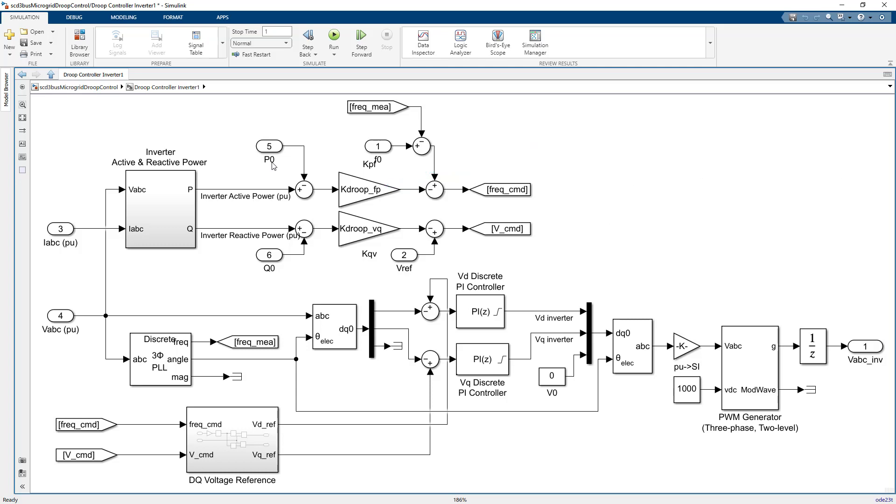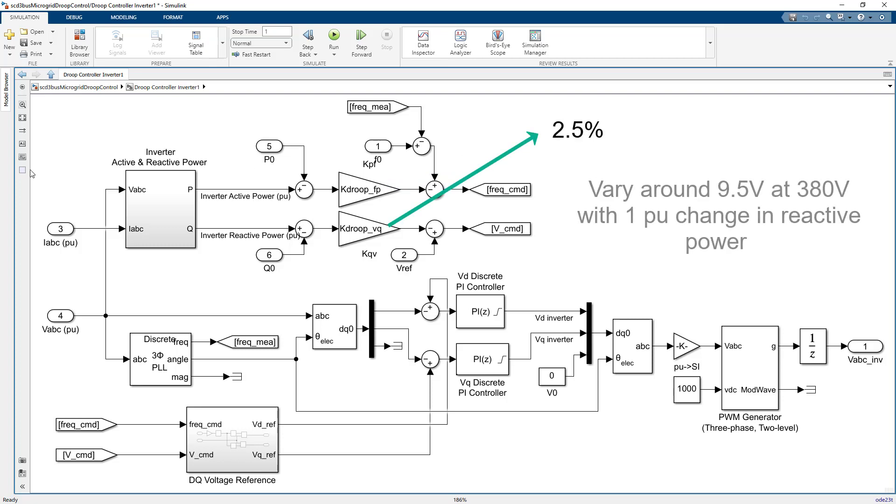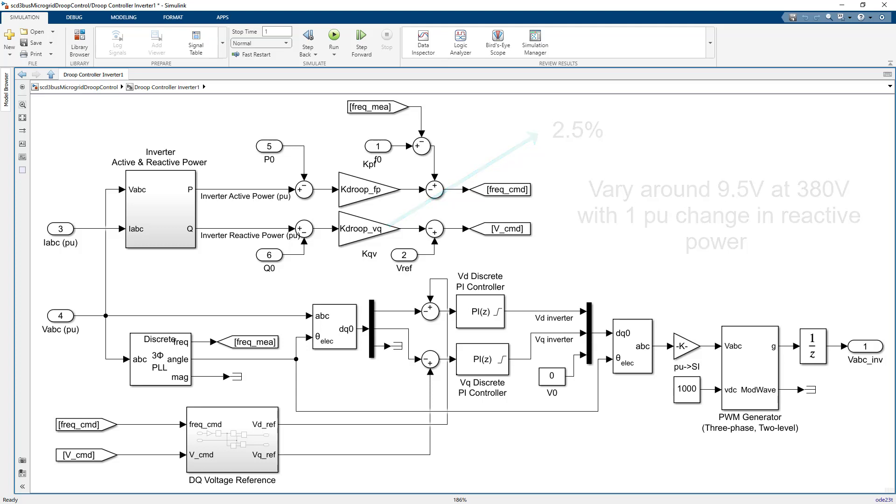The reactive power voltage droop coefficient is also set to 2.5 percent, meaning that the voltage at each point of common coupling bus is allowed to vary over a range of 9.5 volts around the nominal 380 volts with one per unit change of reactive power.